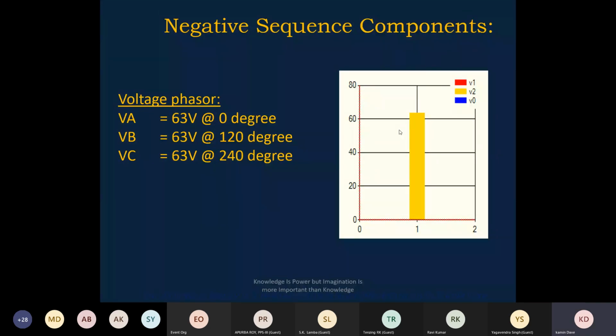So we understand that if it is 100% phase reversal, severe heating will start in the induction motors during start conditions. Normally start condition and run condition, any condition. If it is 100% phase reversal, it is a locked rotor condition, and severe heating will start in the motors.